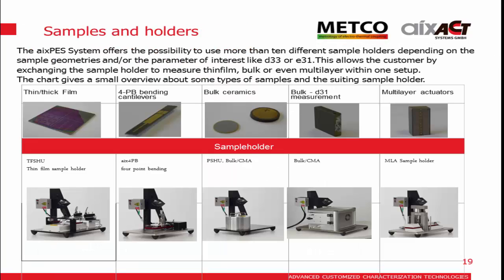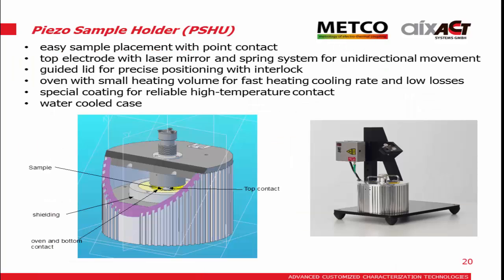So for different sample types we have different sample holders. For the typical bulk ceramics, we have a sample holder which establishes a point contact, and for multi-layers we have sample holders which allow to apply a force. So the sample holder has to be adapted to your sample shape, basically. And the laser interferometer can be attached to the various sample holders for the evaluation. So this is the sample holder for bulk materials.